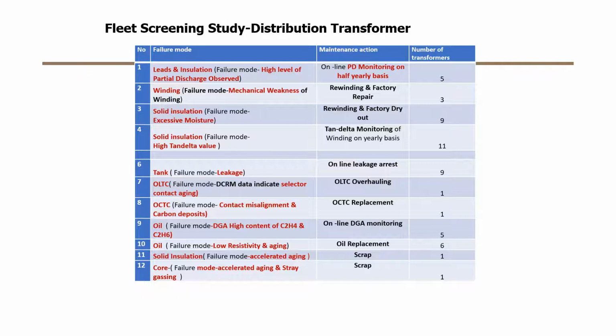Either you do factory dry out, or if possible do the on-site dry out, but don't leave it. If you're leaving it, it's not good. Even flashover can happen because of the excessive moisture and the bubbles inside the transformer. Again, solid insulation failure mode could be high tan delta value. If you have high tan delta, it's just a benchmarking. You have to monitor it, and after some time you have to discard it, or you do some remedy, like you do on-site dry out, you do some kind of overhauling and try to manage the tan delta value if aging is at a moderate level.